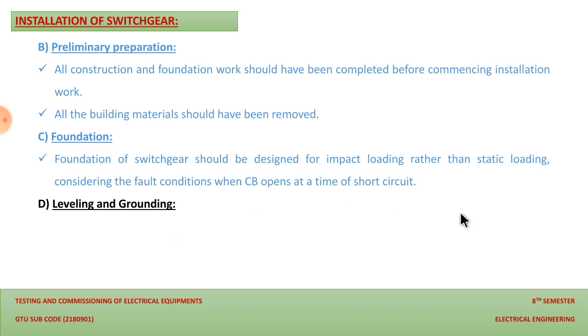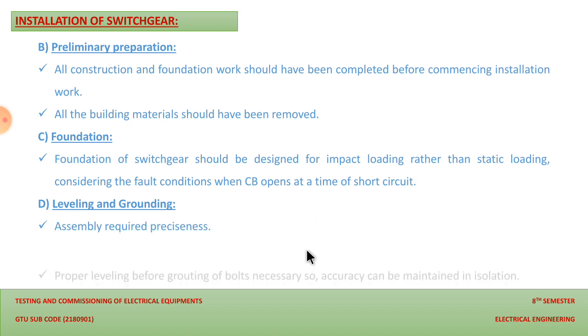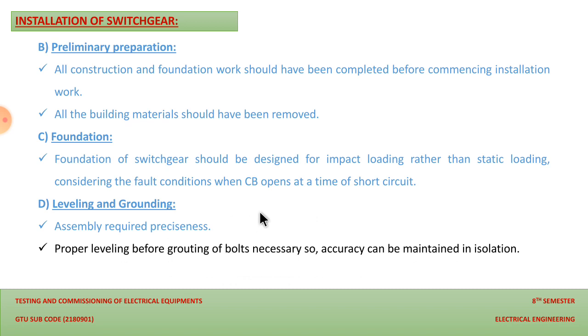Then the next point we should keep in mind for the installation of the switchgear is leveling and grouting. So this is related to the civil work, but leveling and grouting is necessary to install our switchgear with a proper alignment. The assembly requires preciseness while we are installing our device, so proper leveling and alignment are needed. That's why it requires preciseness. Proper leveling before grouting of bolts is necessary, so that accuracy can be maintained in isolation.